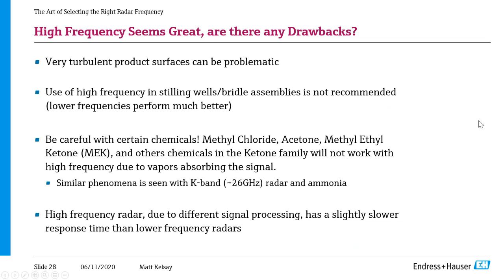You've also got to be careful with certain chemicals and frequency. Things such as methyl chloride, acetone, MEK, and other solvents in that ketone family will not work with high frequency 80 gigahertz radar. This is due to a phenomenon where, in that frequency range, the vapors of those solvents are excited. They have a resonant frequency around 80 gigahertz. So when we send out that signal, the vapors absorb all of that signal and there is no signal return. If you have these chemicals as part of your process, or you're just measuring one of those chemicals, you will not want to use a high frequency radar. A lower frequency, 26 gigahertz or 6 gigahertz, will have no problem. You just can't use the high frequency. A similar phenomenon is seen with the K-band, or 26 gigahertz, radar and ammonia. Same lines there. We can use a high frequency in ammonia or a low frequency, just not that middle band.